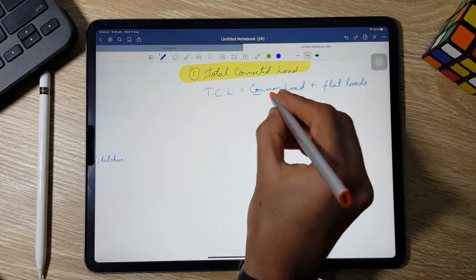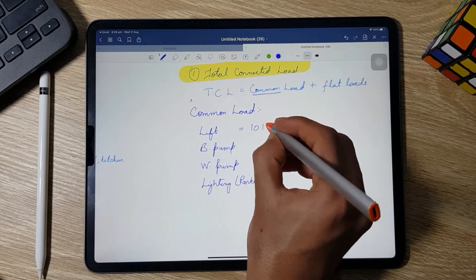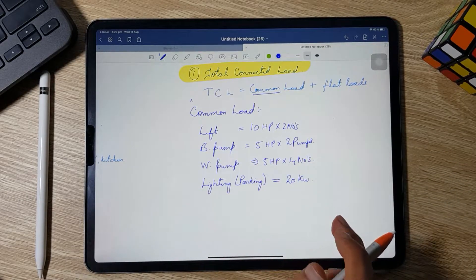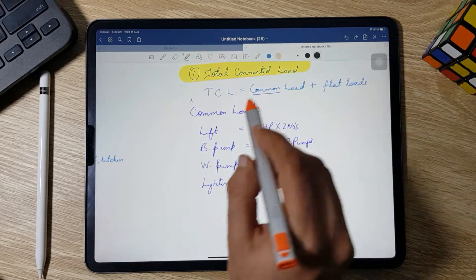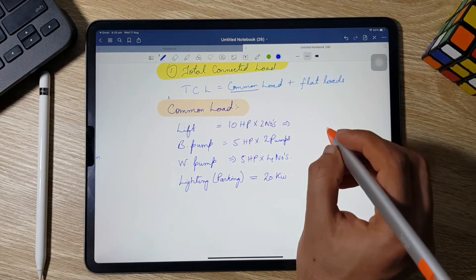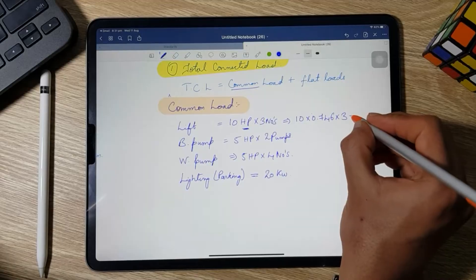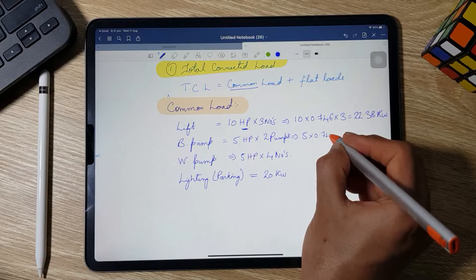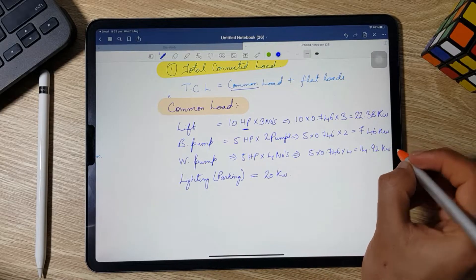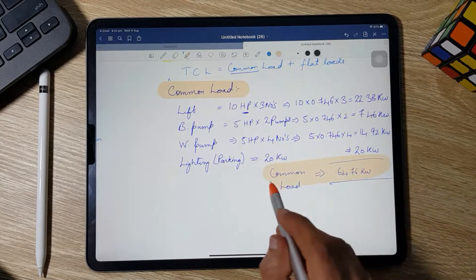Step 1 is the calculation of total connected load, which equals common load plus flat load. The common load includes lift, borewell pump, water pump, and lighting. We are using three lifts each of 10 HP, two borewell pumps each of 5 HP, four water pumps each of 5 HP, and 20 kW of total lighting for parking, lobby, and staircase. Converting HP to kW by multiplying by 0.746: lifts give 22.38 kW, borewell pumps give 7.46 kW, water pumps give 14.92 kW, and lighting is 20 kW — giving a total common load of 64.76 kW.